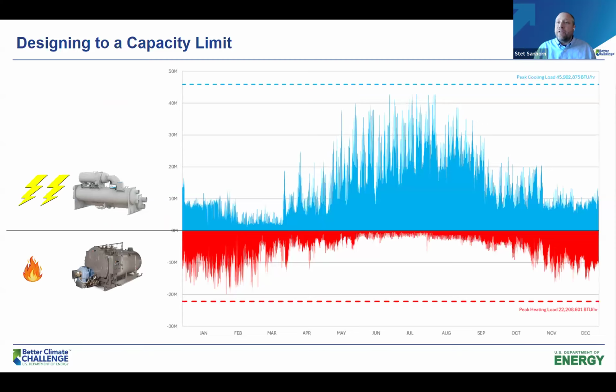So something that might come out of an exercise similar to that, and I love it every time Nora shouts out, put time in your scope of work to get the data, my heart pumps a little faster. Data on how buildings are actually working are critical to making smart decisions, especially in electrification or greenhouse gas reduction retrofits. So this is a graph that we produce all the time for our own clients, where we take measurements from the building for an entire year. If you've got a larger building that has a BMS system, amazing, give us access to the data. If you don't, work with your auditor to put a little CT onto your system, or a flow meter or a BTU meter. There are a lot of non-invasive ones that can get strapped right onto your hot water and chilled water lines. Those can provide us really invaluable information about how your buildings are actually performing.